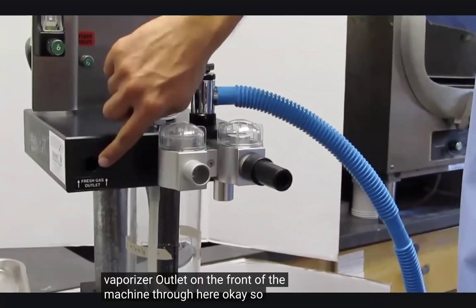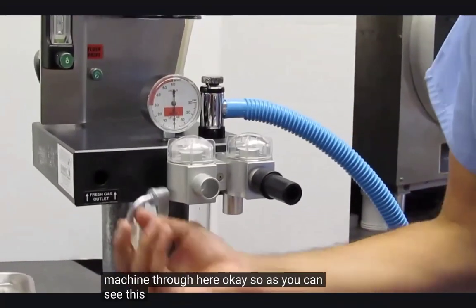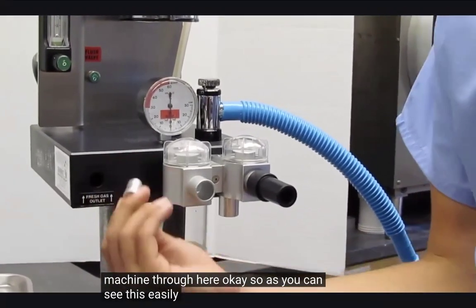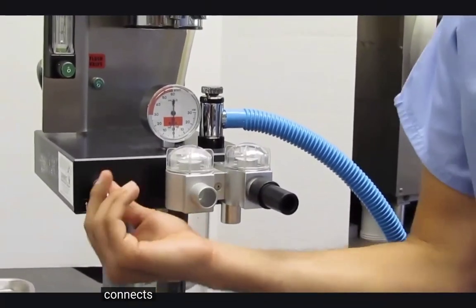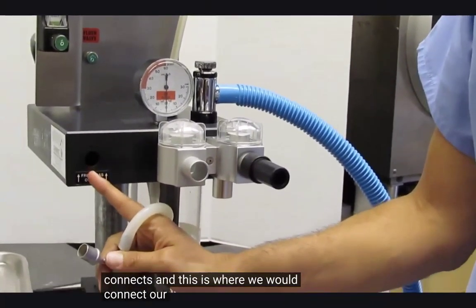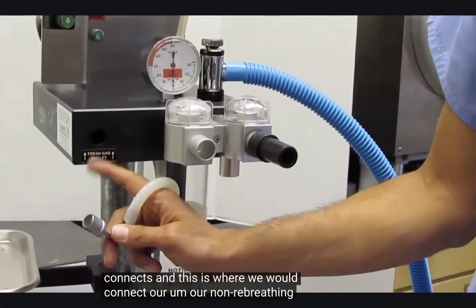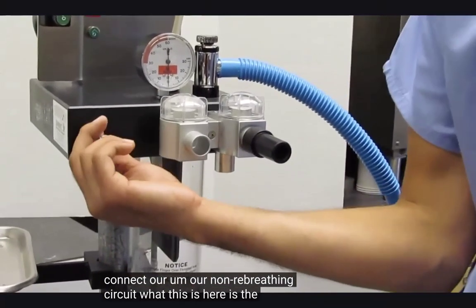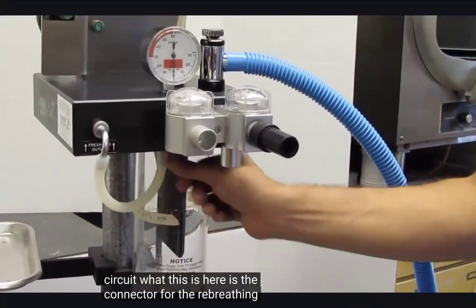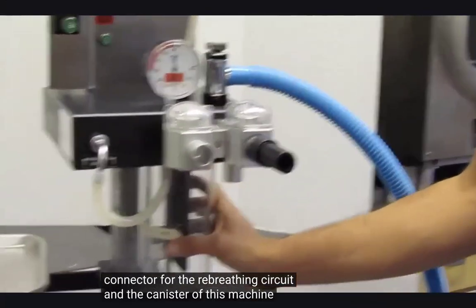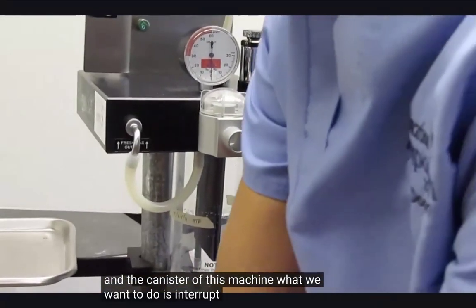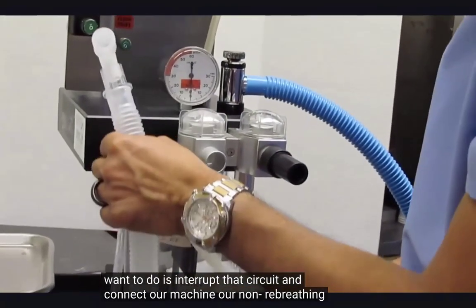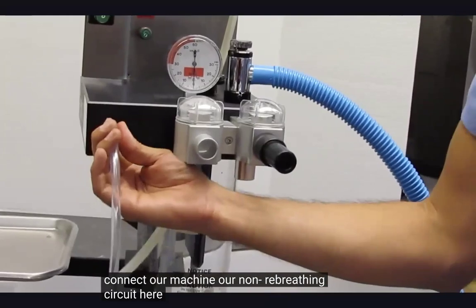As you can see, this easily disconnects, and this is where we would connect our non-rebreathing circuit. What this is here is the connector for the rebreathing circuit and the canister of this machine. What we want to do is interrupt that circuit and connect our non-rebreathing circuit here.